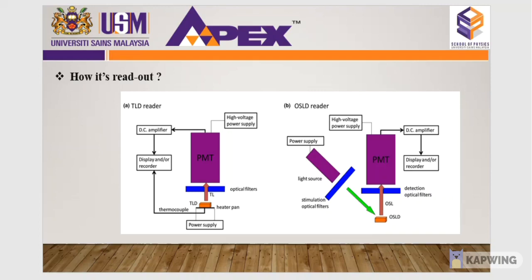In steps 1 and 2, no signal is recorded. The signal is recorded in step 3, when the heat is raised to a high level with enough energy to free electrons from the band gap of the TLD. The luminescence phenomenon happens when the electron moves from the conduction band to the valence band, releasing the absorbed energy.